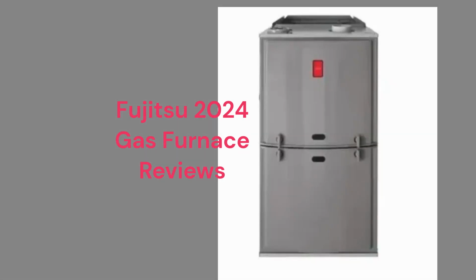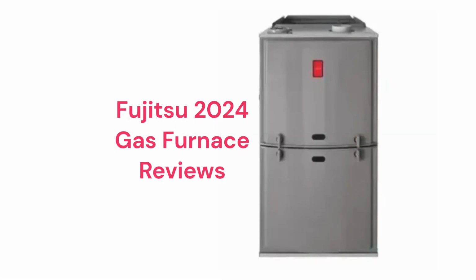This brand is made in Mexico by Rheem Manufacturing for Fujitsu General, and the units are sold through dealers in the USA and Canada. The brand uses aluminized steel primary heat exchangers which resist corrosion but are less durable than brands that use stainless steel. They use direct spark ignition, which is louder and less reliable than hot surface ignition systems.